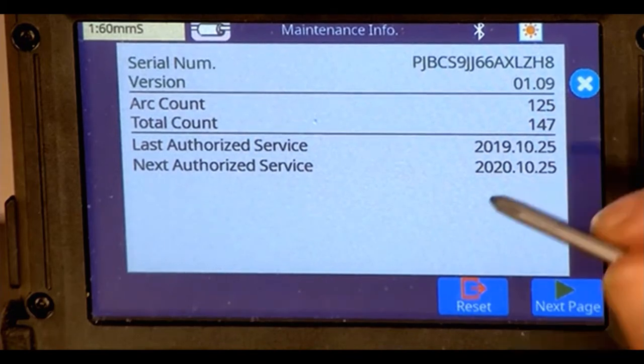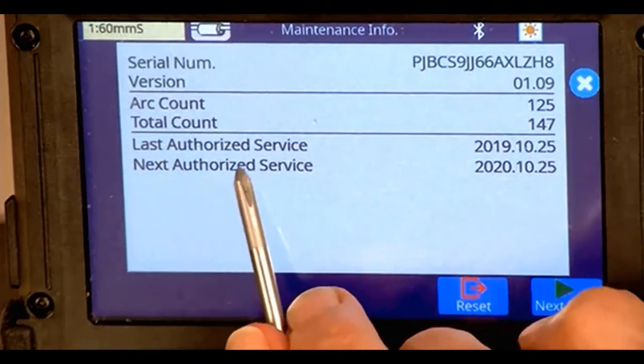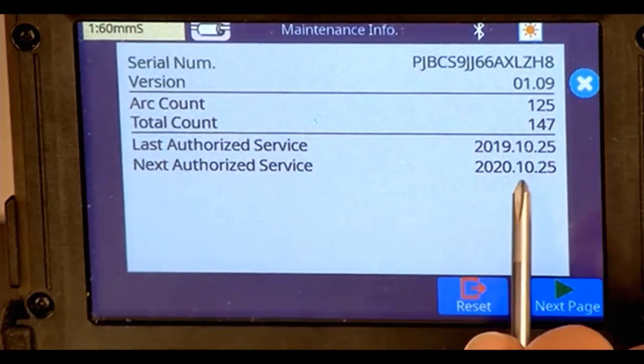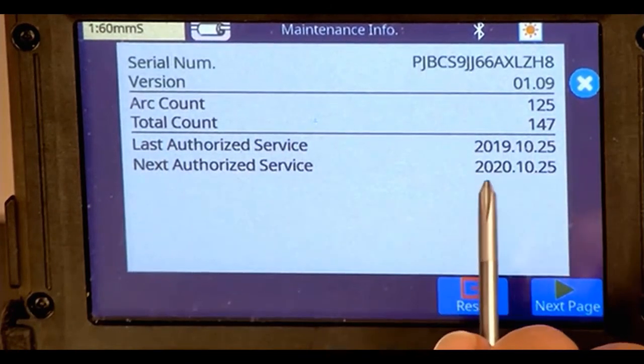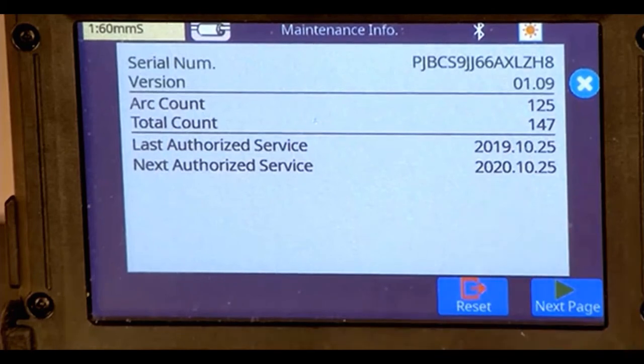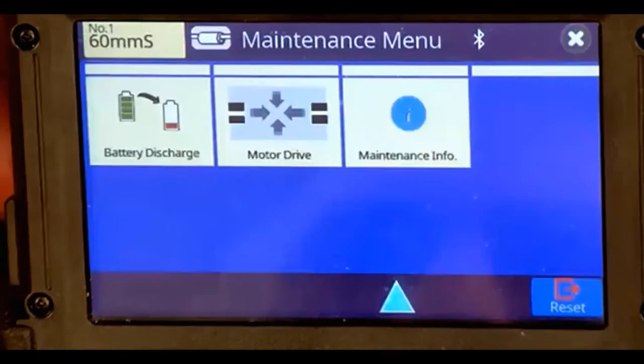Down here, if you wanted to, you could set a date for the next authorized service. What it would do is when it comes to that date, it would tell you to send it into AFL. Most people don't use that because if the splicer is working well, why would you want to send it in? There's no need for that. And if it's not working well, the first thing you're going to want to do is call that 800 number and see if we can find a way to fix it over the phone. So most people aren't going to use that.